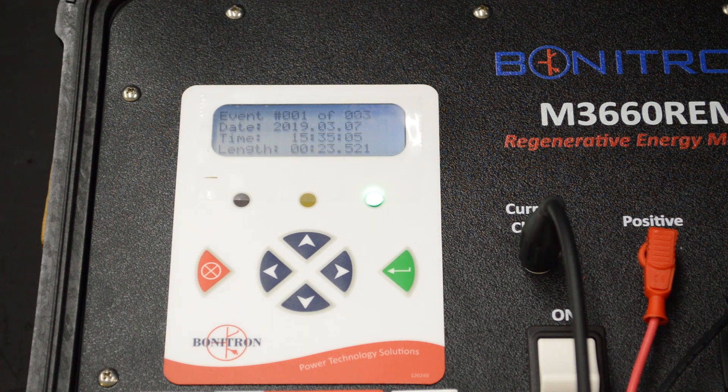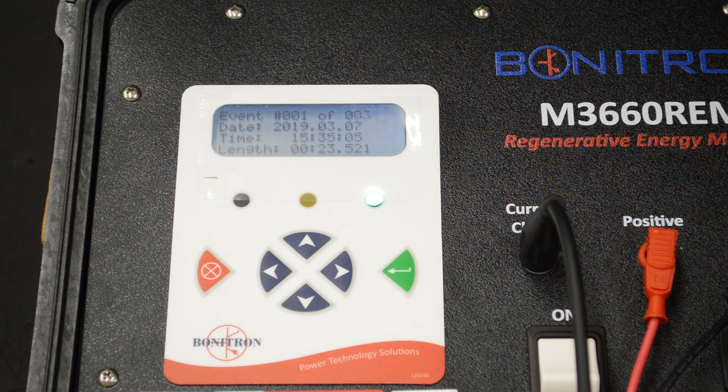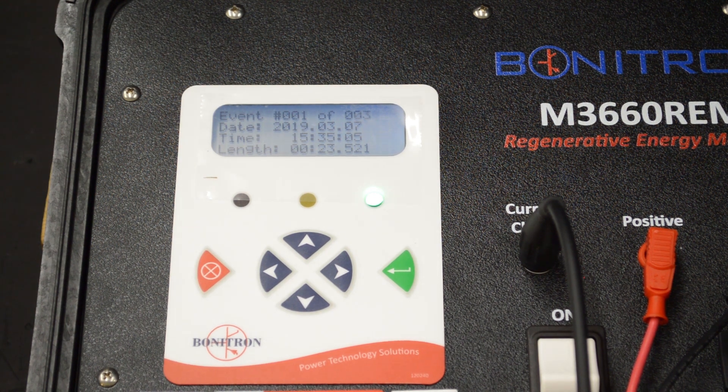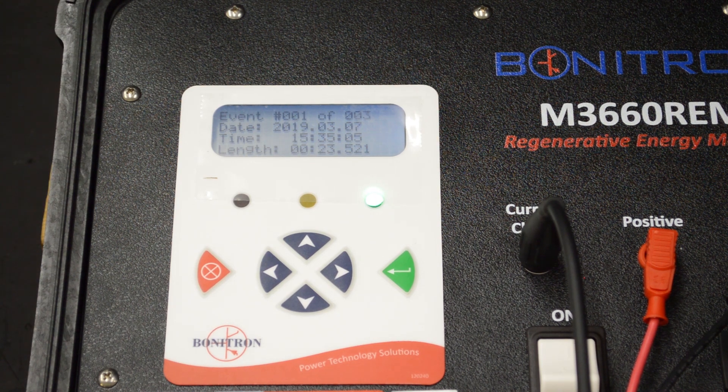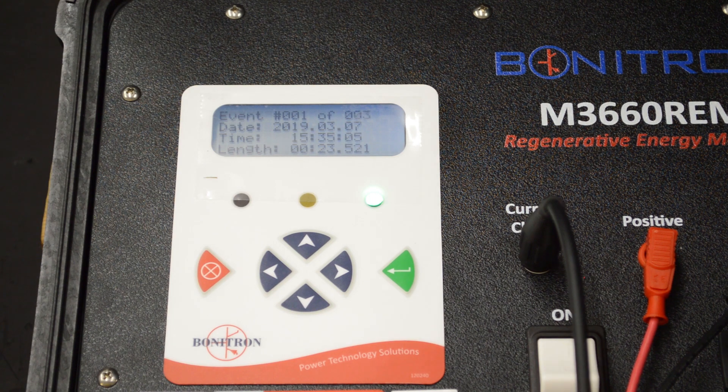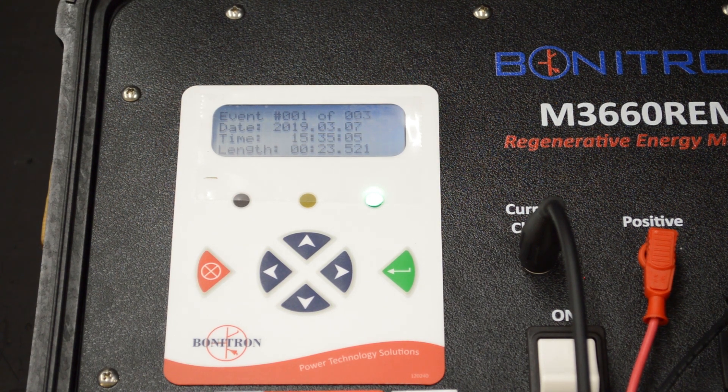Also, if you don't have a braking transistor and resistor connected to the drive in the DC bus, you can provide a load bank with this unit and use it without the braking transistor, and monitor regen events if you're trying to determine what kind of regen solution you might want.